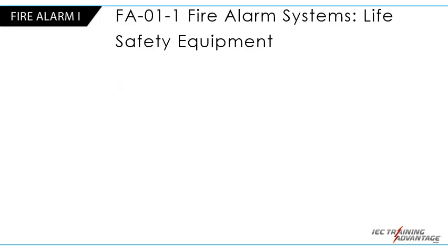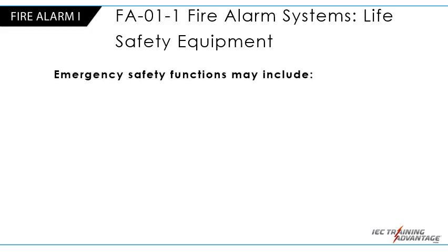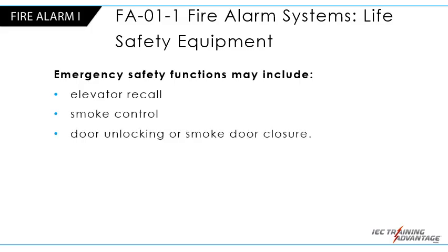Fire alarm systems are capable of far more than just making noise. They detect fires or other hazardous conditions, such as carbon monoxide, and report the signal to the occupants to allow them to evacuate safely. Other functions that fire alarm systems may operate are emergency safety functions, and they may include elevator recall, smoke control, door unlocking, or smoke door closure.